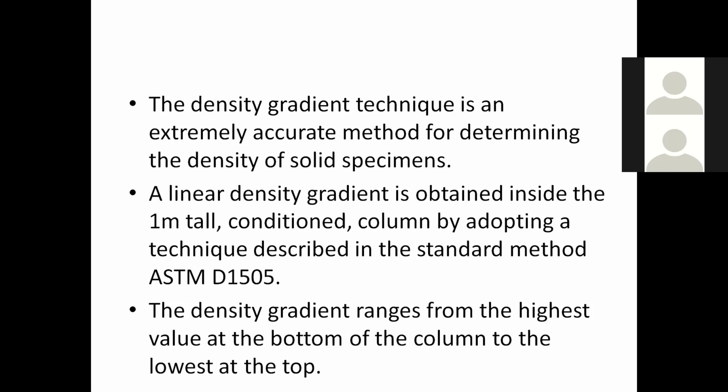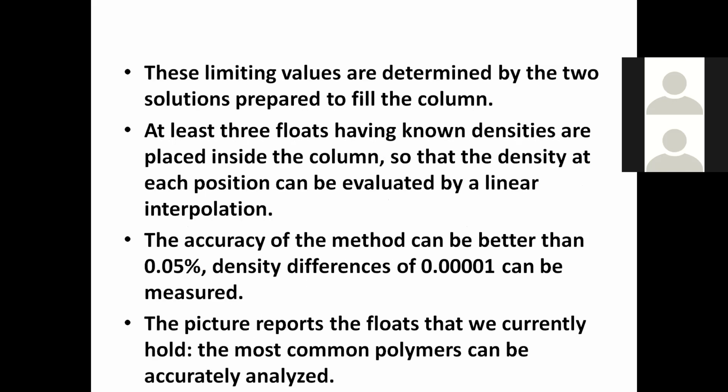The density gradient ranges from the highest value at the bottom of the column to the lowest at the top. These limiting values are determined by the two solutions prepared to fill the column. As I have mentioned, at least 3 floats having known densities are placed inside the column so that the density at each position can be evaluated by linear interpolation.